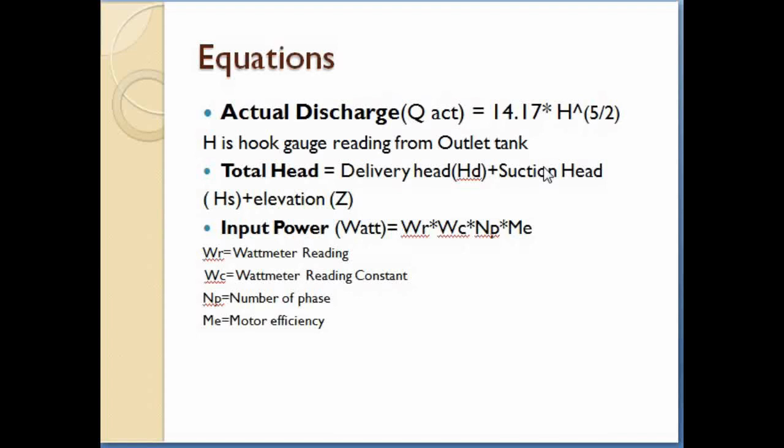Next, total head. There is head developed, so actually the power will be accounted based on how much head the water is lifted. We can count that head by adding the delivery head, suction head, as well as the elevation. If the pump is at a certain height, that elevation is also considered from the water surface.